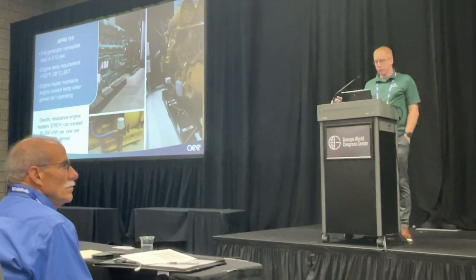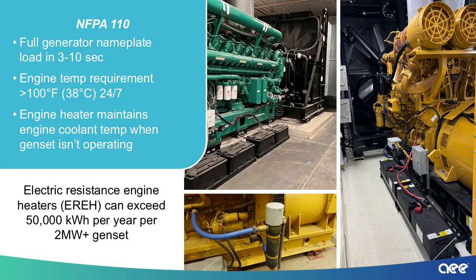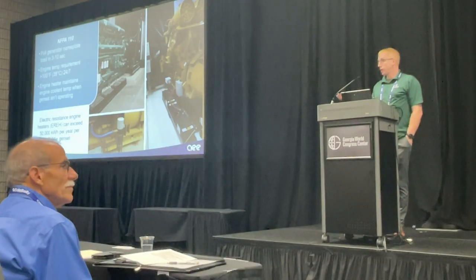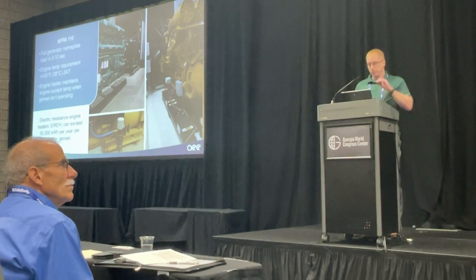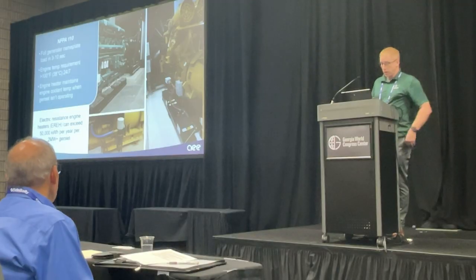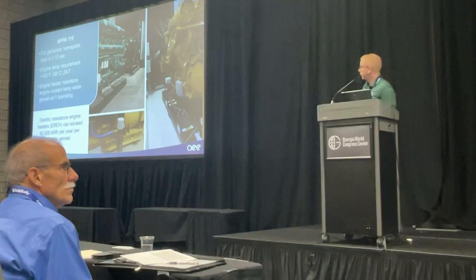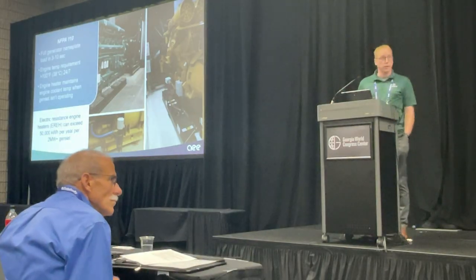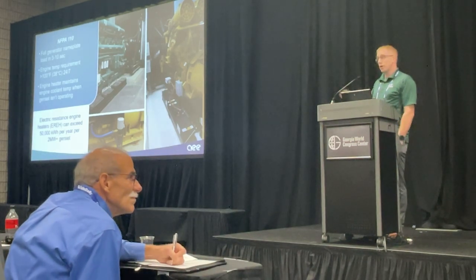Most building or facility owners don't actually know how much energy their backup gensets are consuming day-to-day. For context, NFPA 110 requires that all backup systems provide power at full generator nameplate loading within 10 seconds. That's only accomplished when the engine is already warm, over 100 degrees Fahrenheit. To do that, the OEM has installed electric resistance heating on the engine, constantly running to keep it above 100 degrees. You can see those heaters here, maintaining the engine coolant temperature and circulating it throughout the engine. We're talking about saving 50 to 80% of the energy usage of those electric resistance engine heaters using an alternative engine heating process.